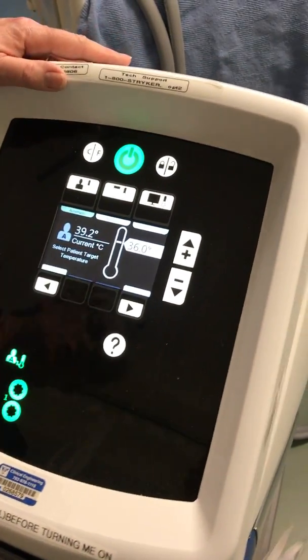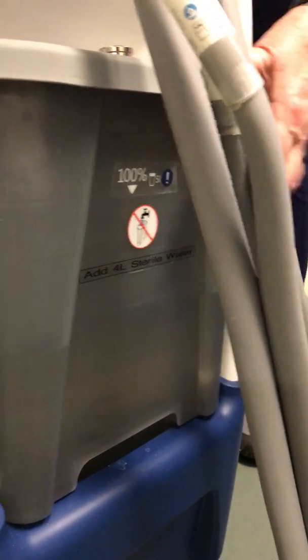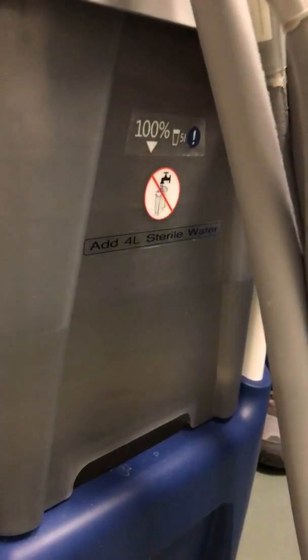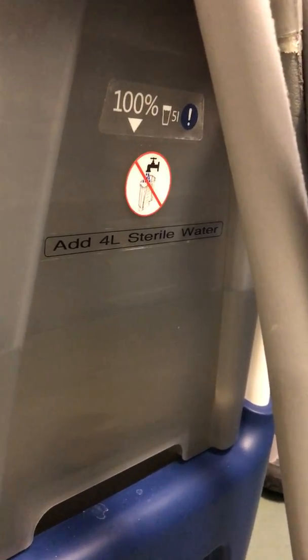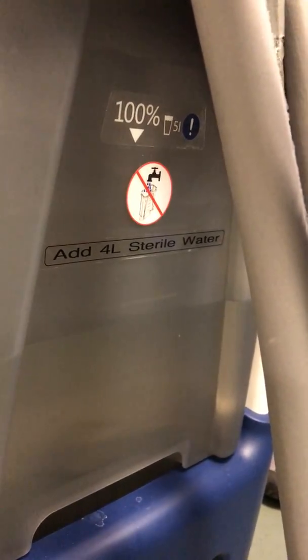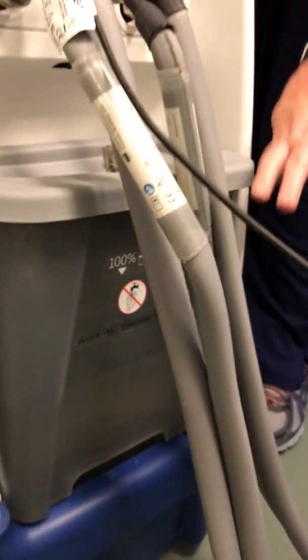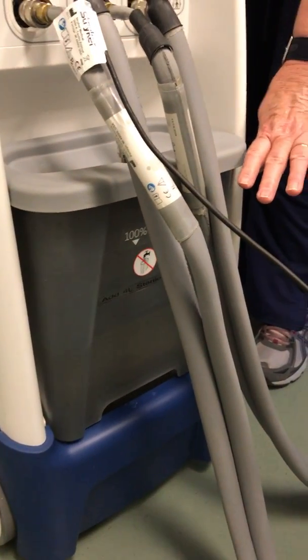Now, some of the things to remember is when you're filling up, you've got your reservoir right here. That has to be at maximum before you start. You make sure that that is at maximum. You fill it with sterile water. So, and it lifts in and out, and you leave the water in there after you've done filling the patient.